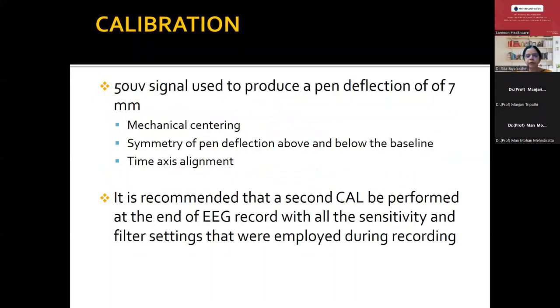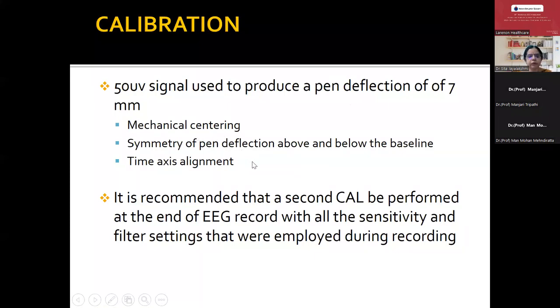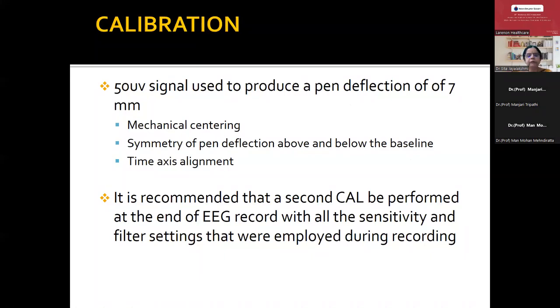Once we know all this and the signals are coming, we start recording on the digital machine. Most important when starting is calibration — calibration has two parts: mechanical calibration and biocalibration. Mechanical calibration is normally done by all technologists before starting by giving a 50 microvolt signal from the machine, which will produce a pen deflection of around seven millimeters. In the analog machine, this ensures all pens are aligned properly; in a digital machine, we look at the symmetry of deflections. A second calibration should be performed even at the end of the EEG recording to make sure alignment is still maintained during the 40 minutes of recording.